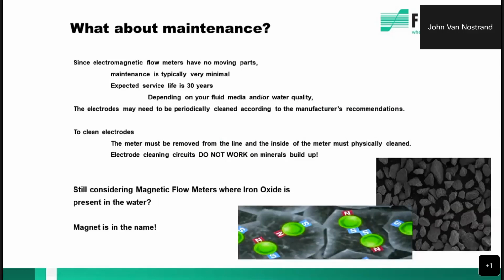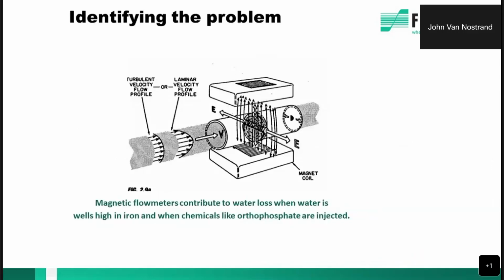So what happens with this magnetite is it actually coats the inside of a magmeter, creating a short between the electrodes. So when we look at how a magnetic flow meter works, we have electrodes. It works on the principle of Faraday's law. There are electrodes on both sides of the meter, and then there are coils around the other opposite sides. So we're basically inducing a magnetic field.